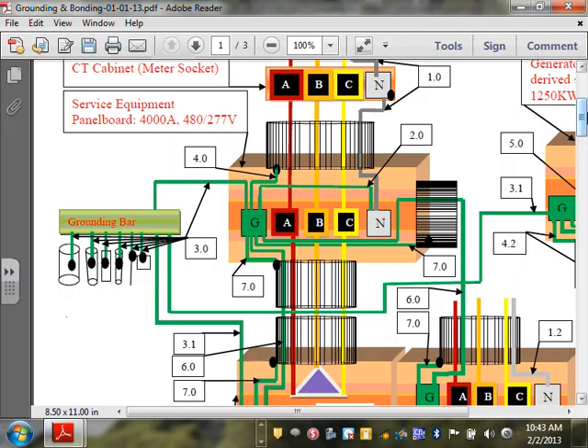So we covered this one, my friends, right? Number 3, we covered number 2, number 1, all this. Now I'm going to go to the easier branch. I want to branch off right here and go to a subpath. Any question about the main? So the main service, the code says the following. In the main service, you have to bond the neutral, and then like we did right here, your neutral must be bonded to the enclosure where the main circuit breaker is located. That's what I did. We bonded here to here, and this is also bonded to the enclosure, right?